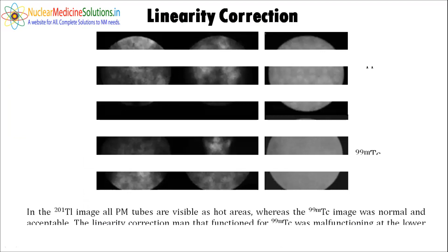This is an example where you can see that without the linearity correction map, it is showing a cold area. After applying the linearity correction map, this cold area disappeared from the image, and the image becomes perfectly uniform, a good image. This is the second example. This is the image where we have not applied a linearity correction map while acquiring the image. It is showing a cold area in the image, which is due to the linearity correction map we have not applied.